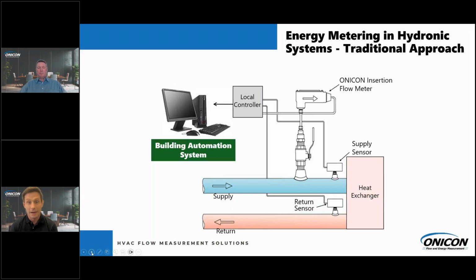As we provided these meters for these applications, we realized we were getting a lot of calls back saying, "Hey, your flow meter is not as accurate as you say it is." What we would do, we would have them bring it back, we would test it, verify it, and it was within the accuracy statement that we said it was. So we decided to look into this problem.